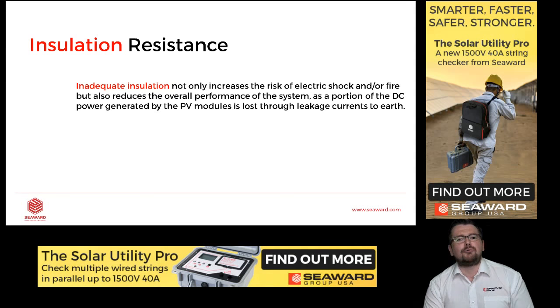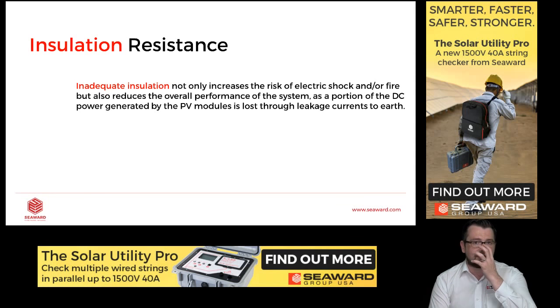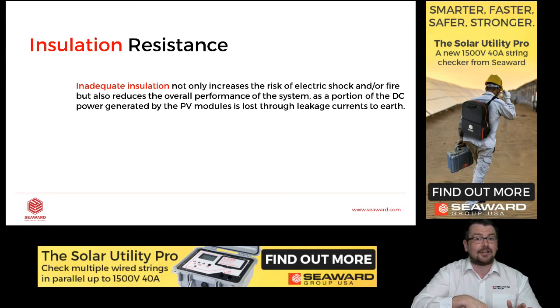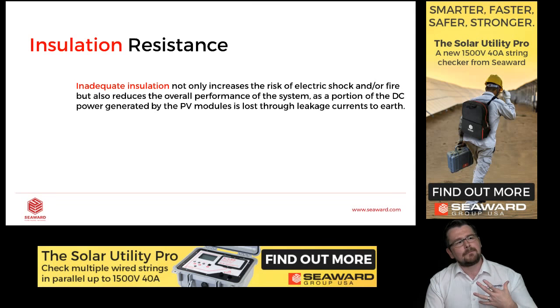A bigger concern really is insulation resistance. Inadequate insulation not only increases the risk of electric shock, but it also reduces the overall performance of a PV system. And a portion of the DC power generated by the PV modules is lost via that leakage to earth. So insulation resistance is a very big concern. So when we're testing PV systems, a lot of people have their own standards, but the IEC standard says that we should look for 1 megaohm of resistance at least.